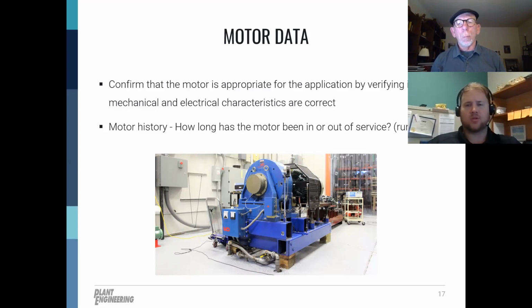Additionally, you're also going to want to confirm the motor is appropriate for the application. You'll compare your motor nameplate, just like motors have nameplates. Also, fans and pumps are going to have nameplates as well. So whatever the load is that your motor's spinning, compare your motor specifications to the load when you're doing some maintenance assessment or replacement.